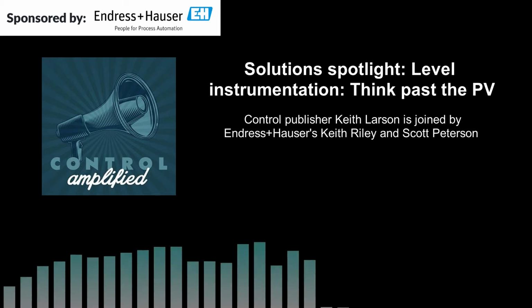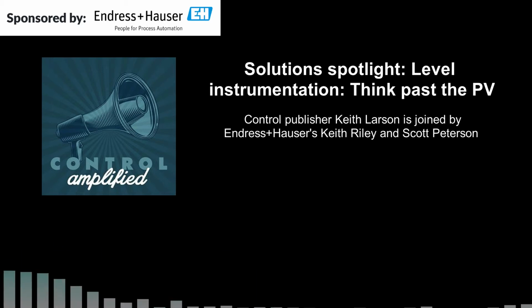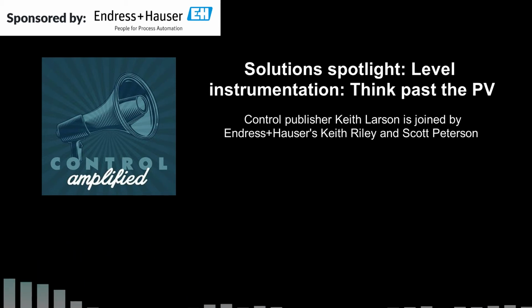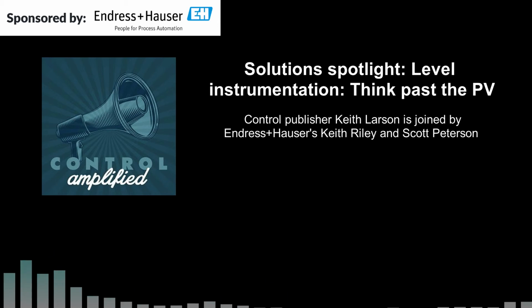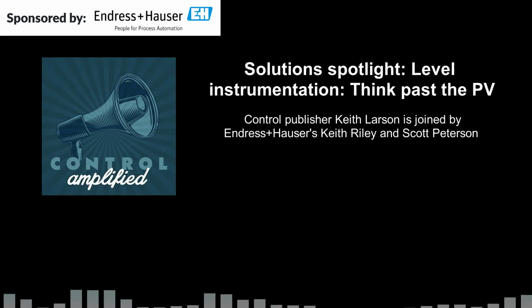What you're finding implemented today is an instrument-guided procedure which leads you through it. You're not actually making any changes to the instrument, but it's asking you questions. Did you check this? Yes. What was the response? You type it in. So that it's leading you through that, making sure you've done all the steps as identified in the functional safety manual. And what's even better is at the end, you can get a PDF of it, so you've got a report automatically of what you just did.